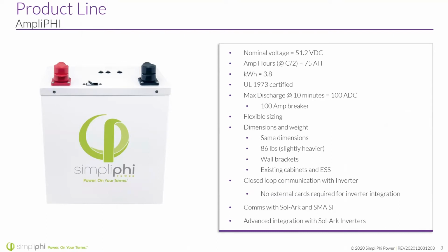Our AmpliPhi battery is a 3.8 kilowatt hour battery, similar to the Phi battery in that it's the same size, basically the same dimensions and weight. So it actually fits existing wall brackets and ESS cabinets that we use with our Phi products. It only comes in 48 volts, not 24. It holds the same UL standard, UL 1973, and UL 9540A now—that's the test protocol when it relates to system level as well.